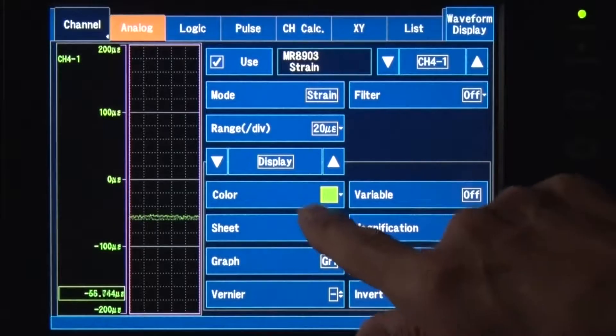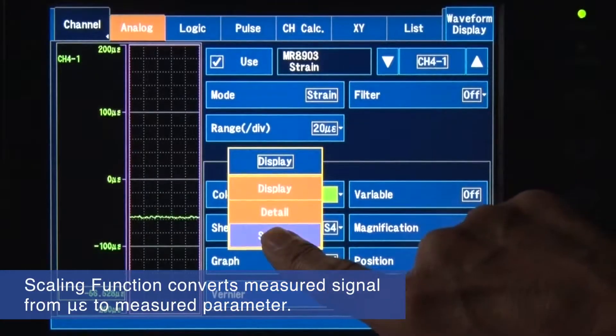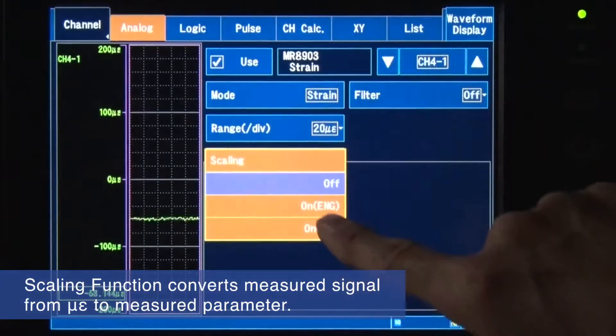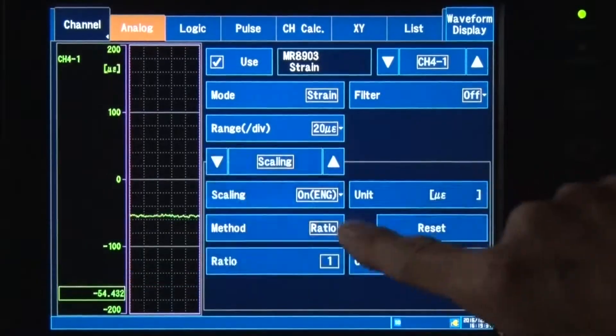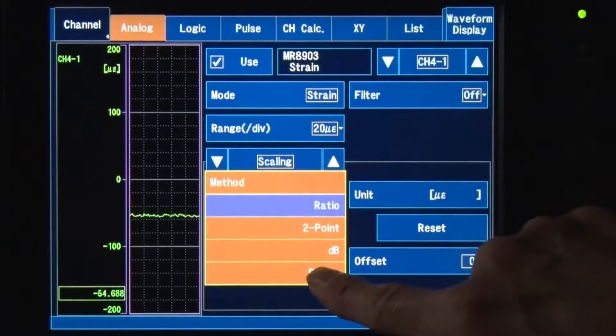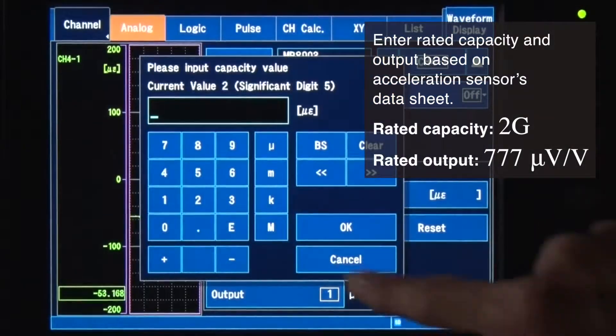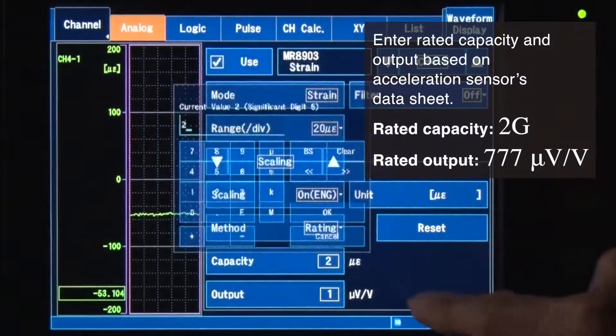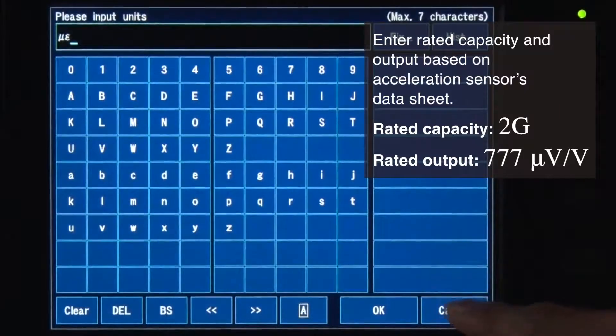The displayed value can be converted from microstrain units to the measured parameter. The measured acceleration is directly displayed. On this screen, enter the rated capacity and output based on the acceleration sensor's data sheet so that the measured acceleration is directly displayed.